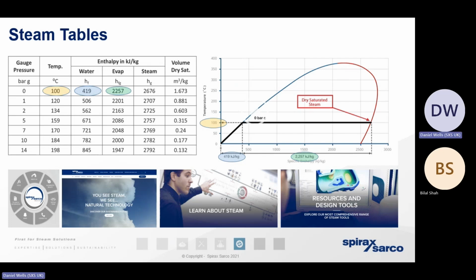So when that kilogram of water is boiled off and changed from a single phase non-compressible fluid to steam as a gas, the rate of expansion is more than 1,600 times. It's huge. So the magic's really happening in these 3 middle columns. It shows us the energy relationship that steam has. The first column shows us how much energy the water needs to contain before it boils. Now, notice here I say how much energy the water contains.